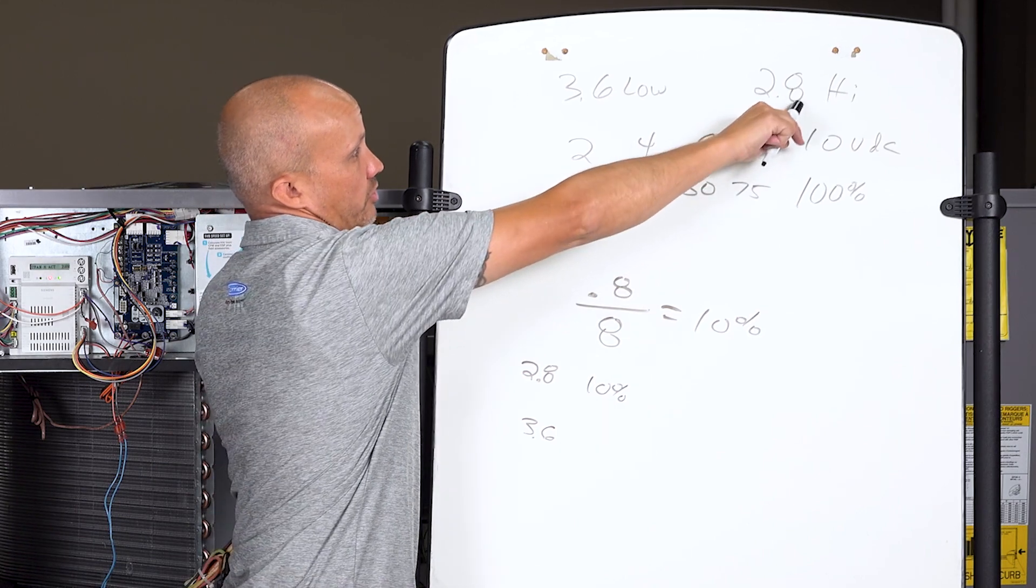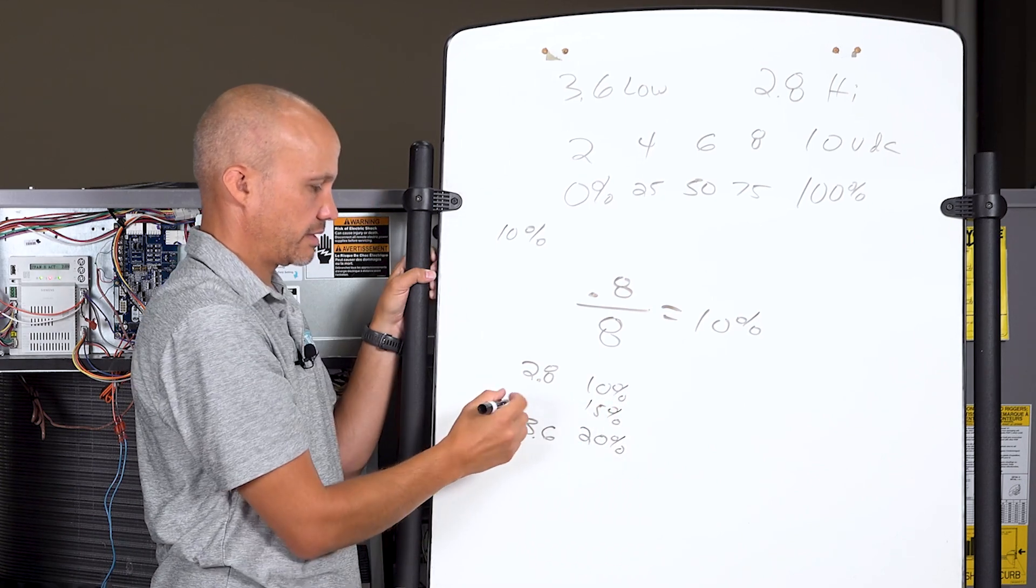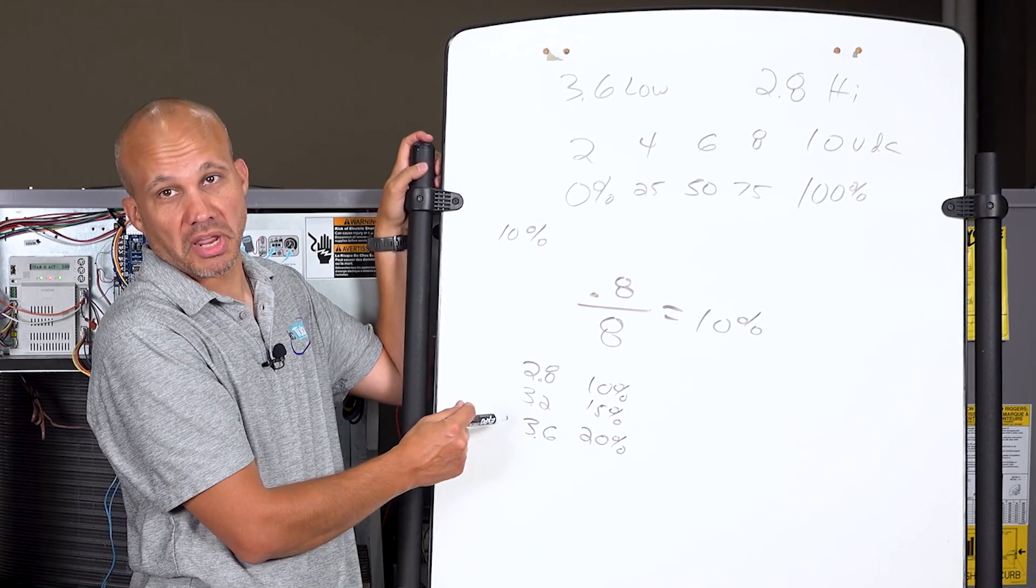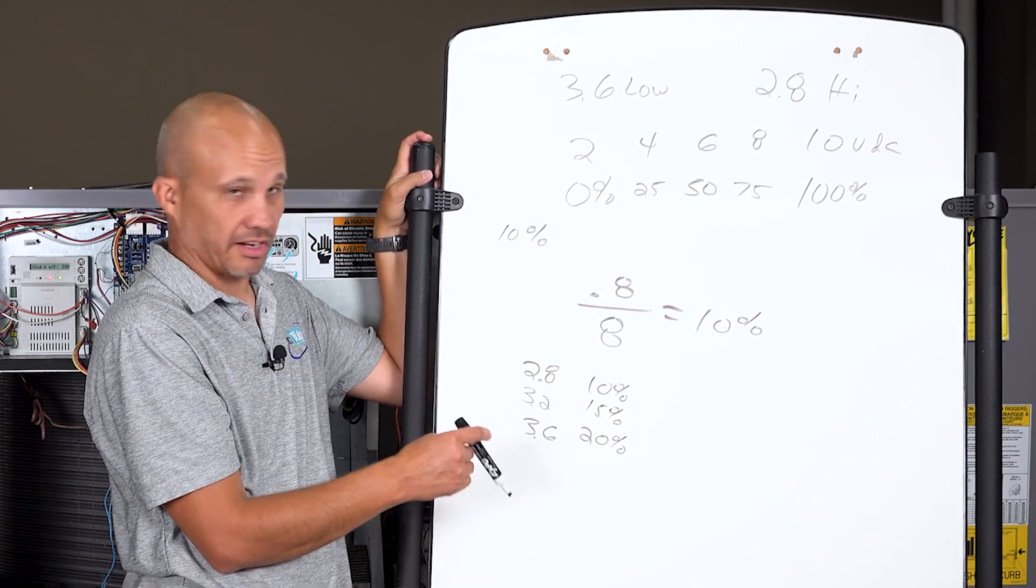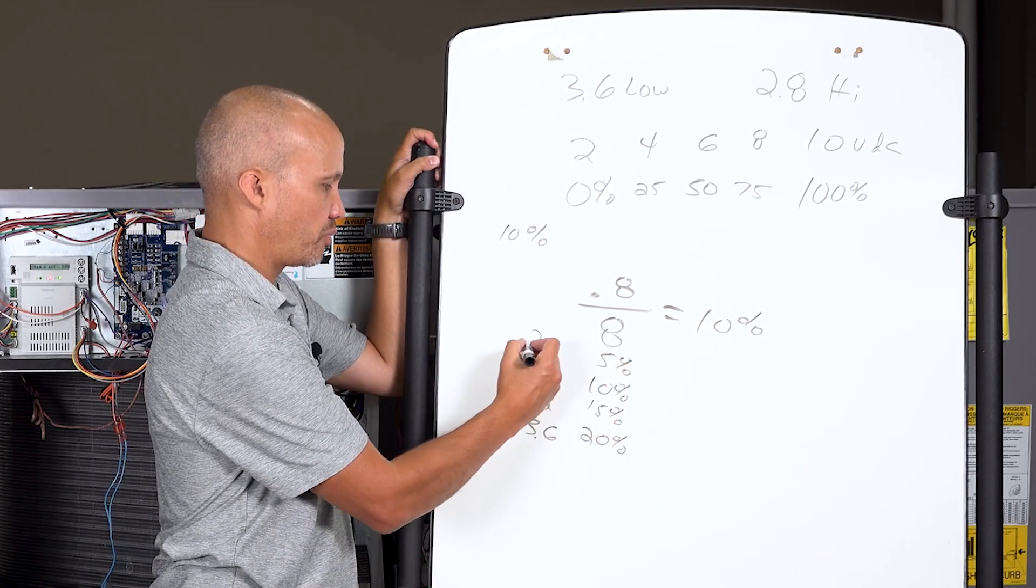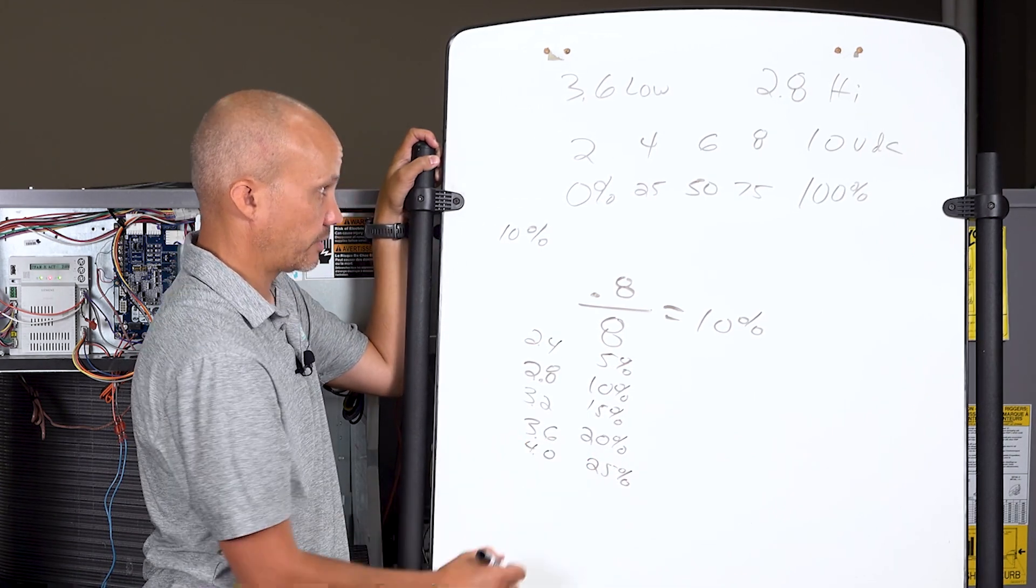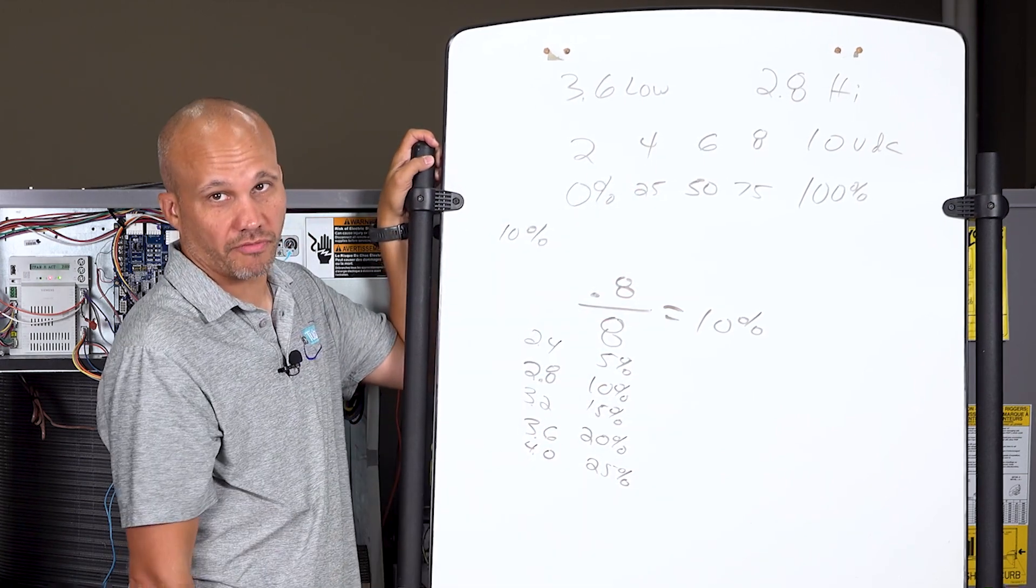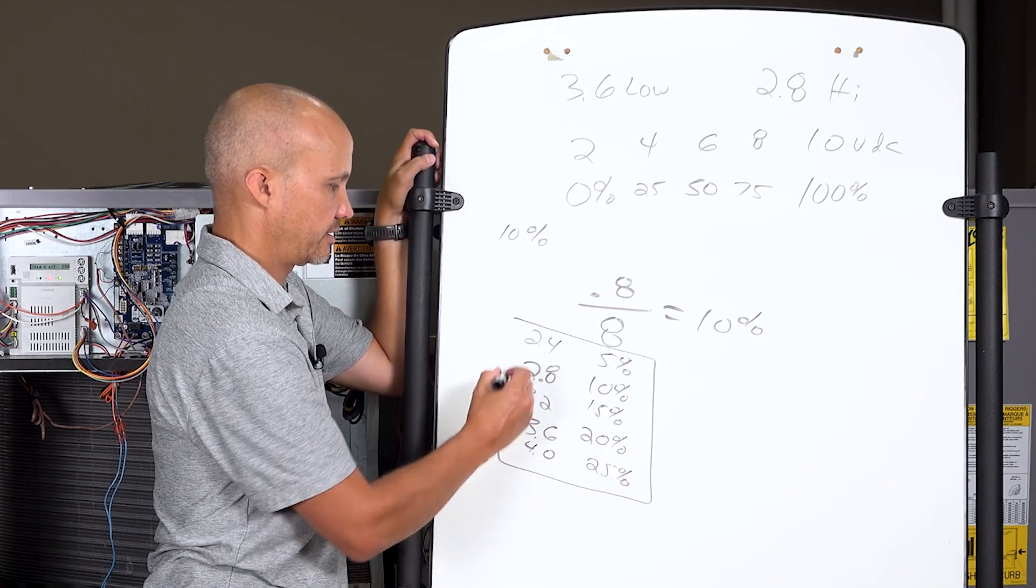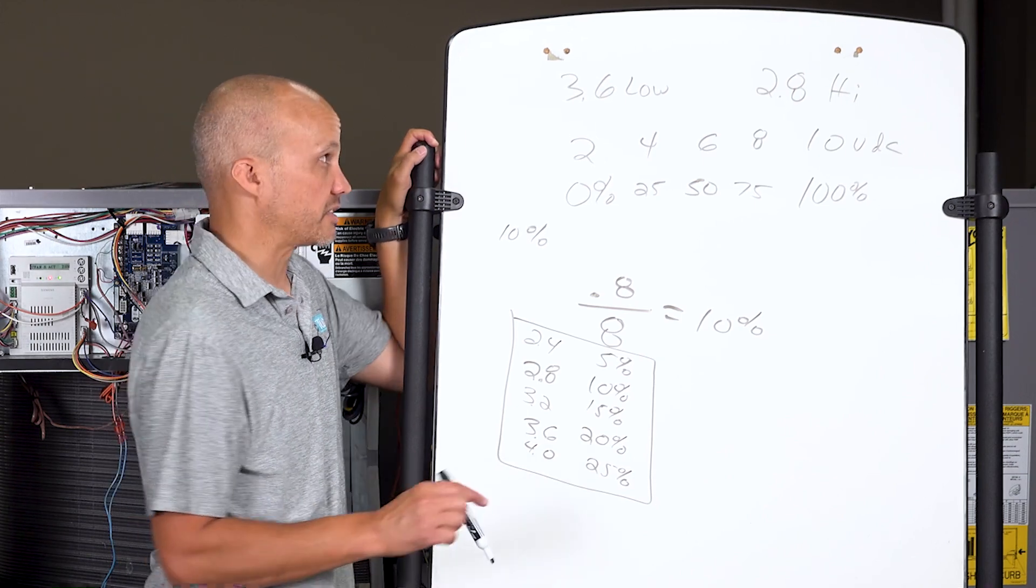If I wanted 15 percent, that would be 3.2 volts. Instead of doing this math all the time, you may want to just make a chart like this once and never think about the math again. 5 percent would be 2.4 volts, 25 percent would be 4.0 volts. You probably should never have more than 25 percent on a rooftop economizer anyway. If you take a picture of that and save it, you don't have to really do this math ever again.